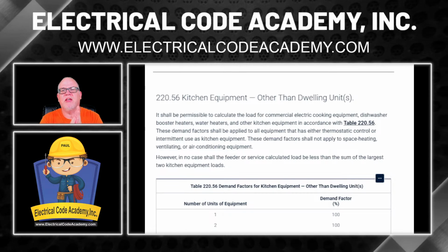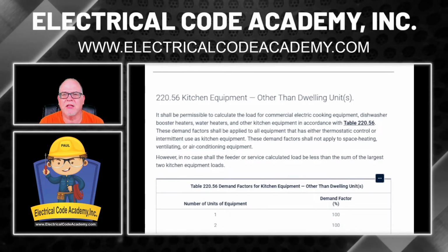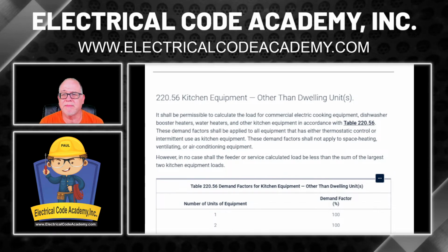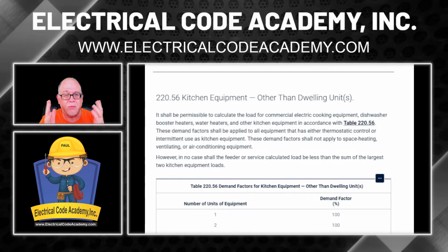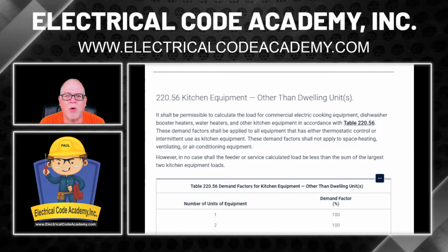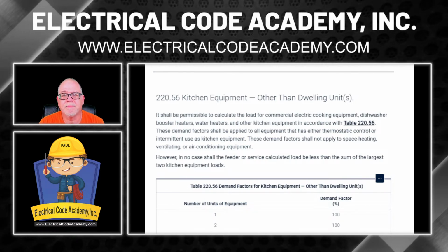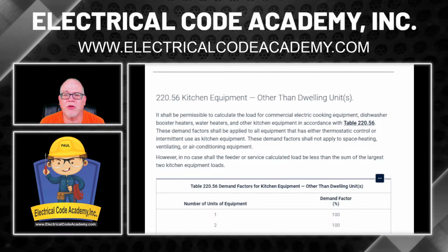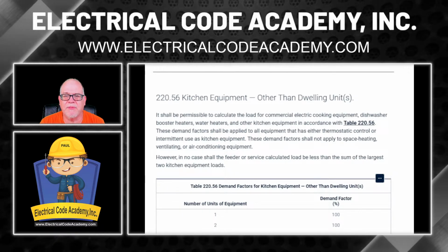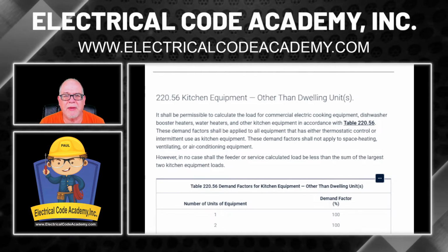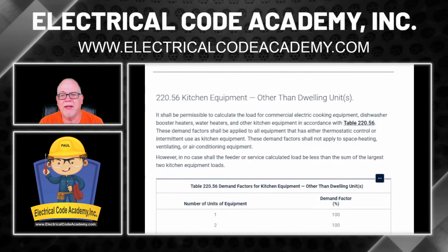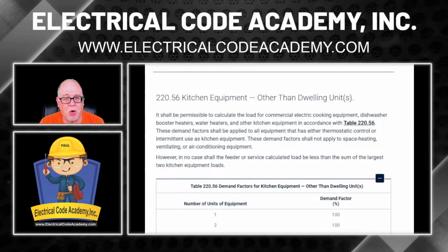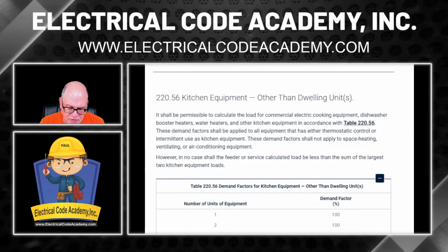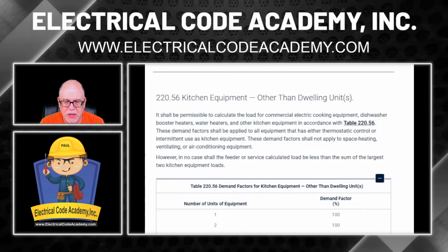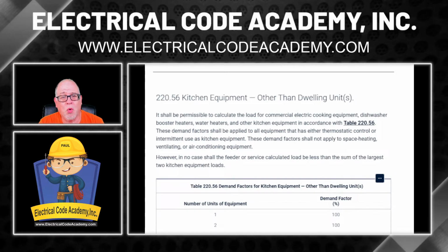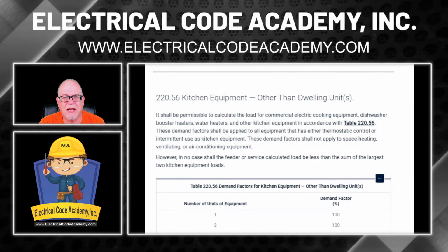Let's read it. It says, it shall be permissible to calculate the load for commercial electric cooking equipment. Okay, so we do have cooking. We have ovens, so we're good there. Dishwasher booster heaters, we do have a booster heater. Water heaters and other kitchen equipment in accordance with table 220.56. It also says these demand factors shall be applied to all equipment that has either thermostatic control, and most of this stuff, the ovens, the grills, the deep fryers, and all that kind of stuff, is going to be thermostatic controlled. It says, or intermittent use in kitchen equipment.